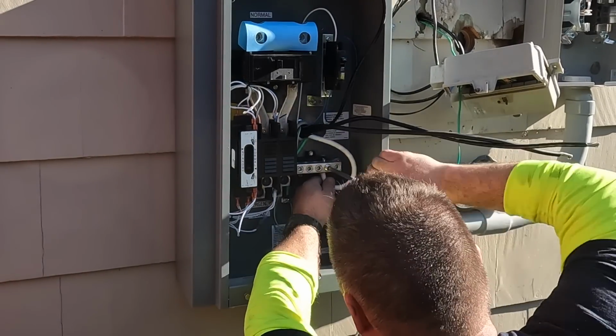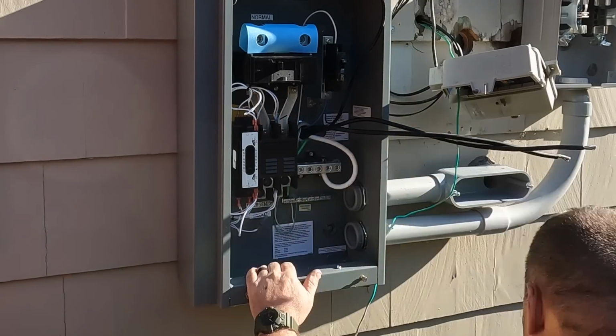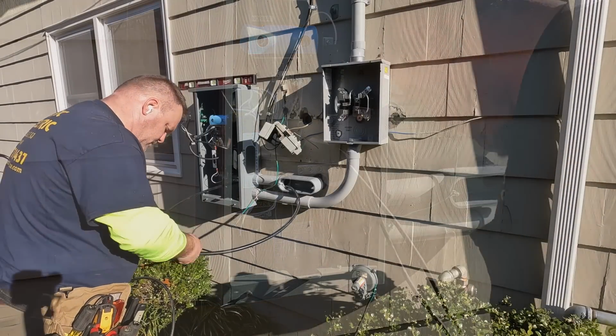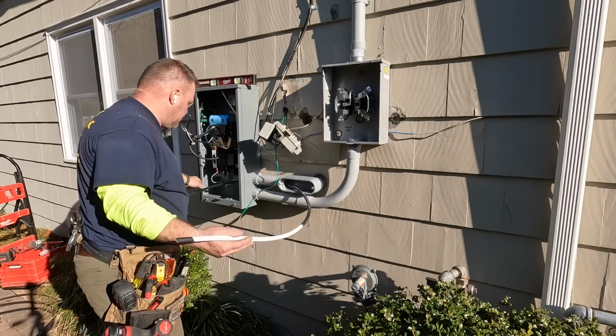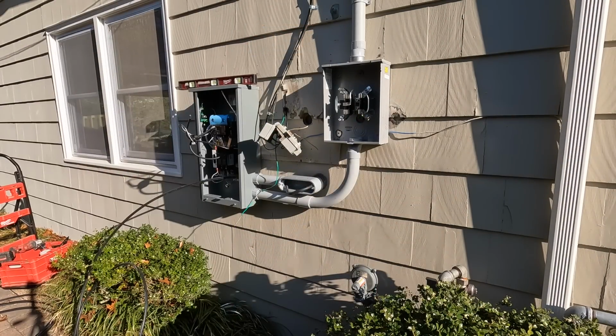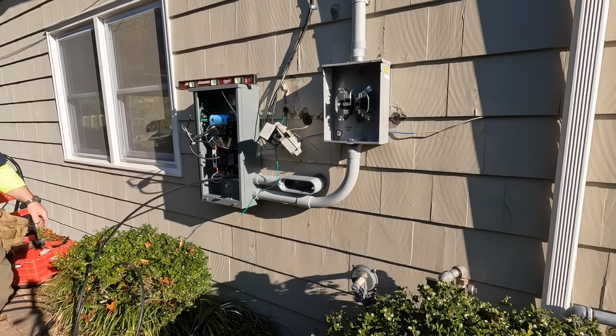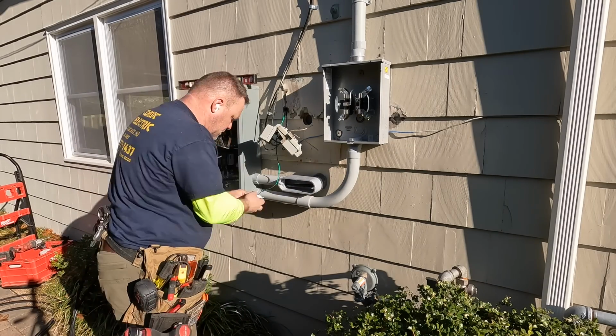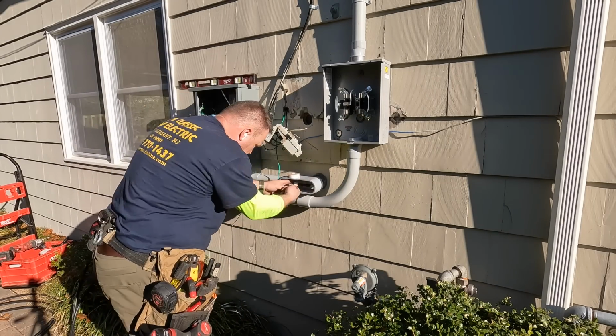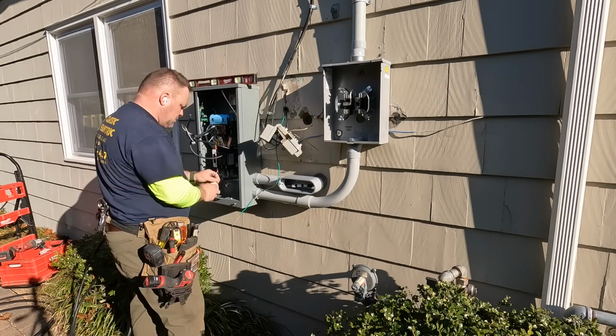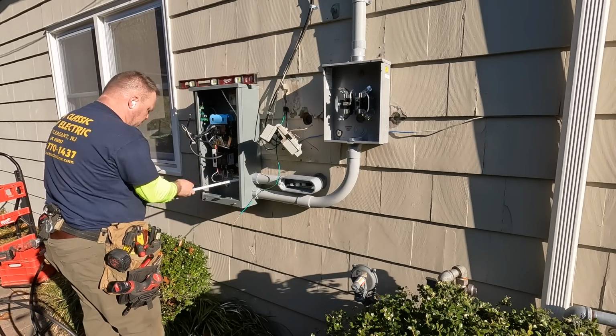And I think the code does address that someplace. I'd have to find that, but it would probably fall under workmanship, Article 110.12, Execute work in a workmanlike manner, but of course they don't define what a workmanlike manner is. So that's up to us and the AHJ, or the electrical inspector here in New Jersey, since we follow the Uniform Construction Code that adopts the National Electrical Code.